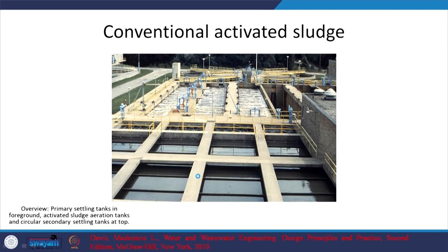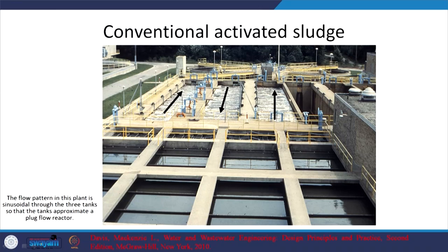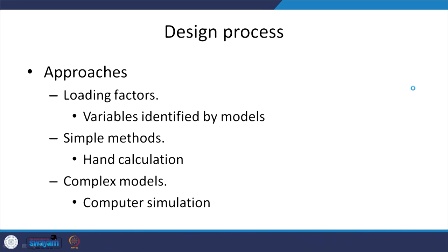Conventional activated sludge: primary sedimentation, then aeration where microbes degrade the substrate, then circular secondary clarifiers. The flow has a sinusoidal pattern to give plug flow characteristics. We noted earlier that plug flow is better than the ideal CSTR. Design process options are: one based on loading factors — simple methods — and more complex computer simulation methods, which we will not cover in detail.